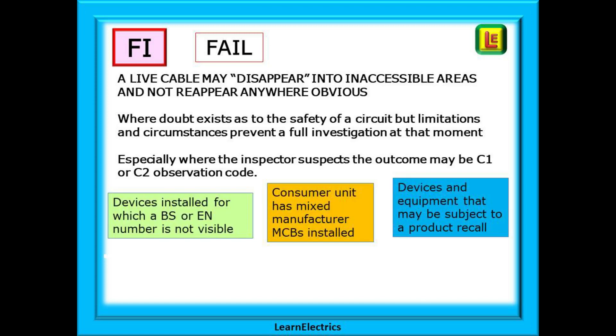A live cable may disappear into inaccessible areas and not reappear anywhere obvious. You may suspect that mixed devices in a consumer unit may not be compatible and want to check further. Use FI where doubt exists as to the safety of a circuit but limitations and circumstances prevent a full investigation at that moment, especially where the inspector suspects the outcome may be a C1 or C2 observation code.